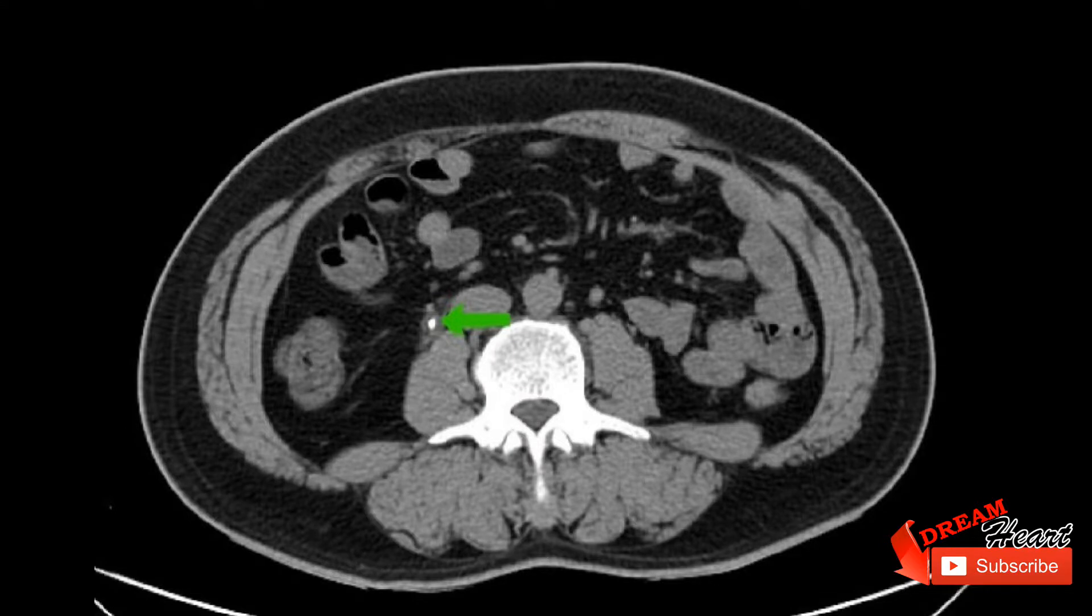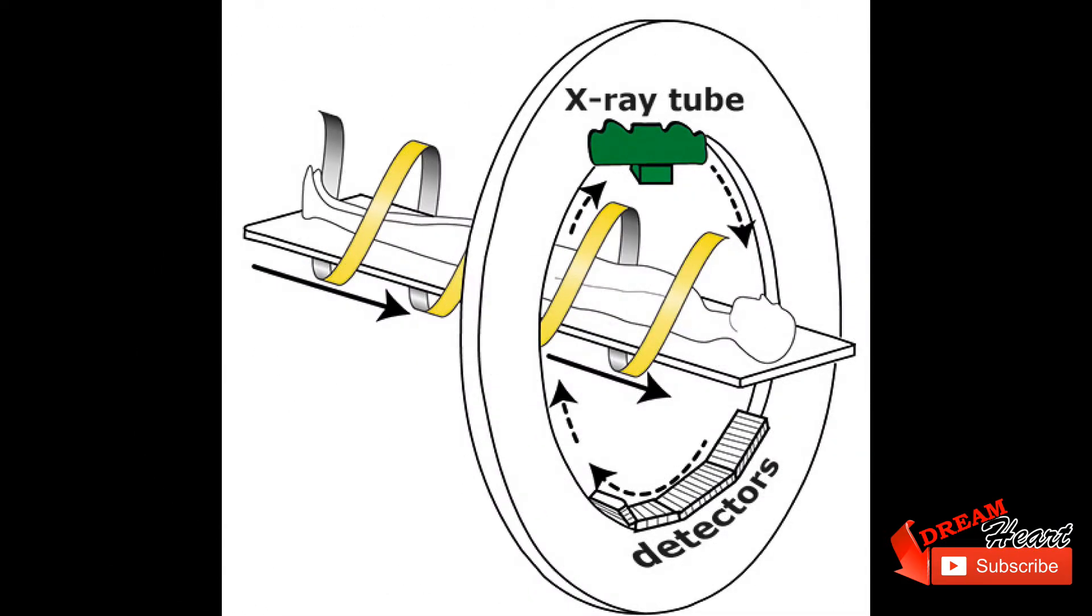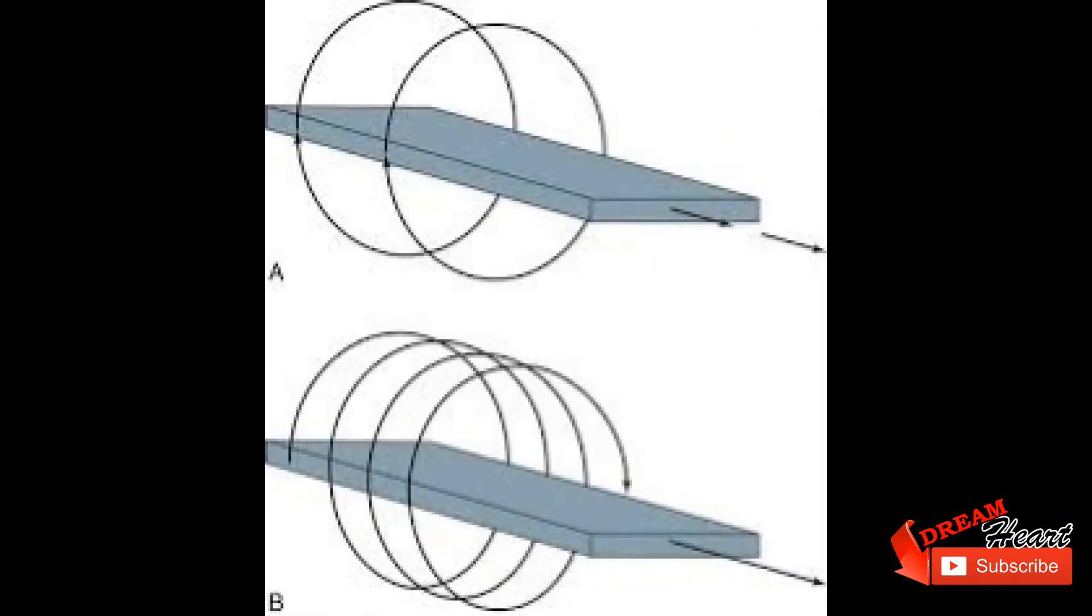Spiral or helical computed tomography was introduced in the early 1990s, with much of the development led by Willi Kalender and Kazuhiro Katada. In older CT scanners, the x-ray source would move in a circular fashion to acquire a single slice. Once the slice had been completed, the scanner table would move to position the patient for the next slice. Meanwhile, the x-ray source and detectors would reverse direction to avoid tangling their cables.